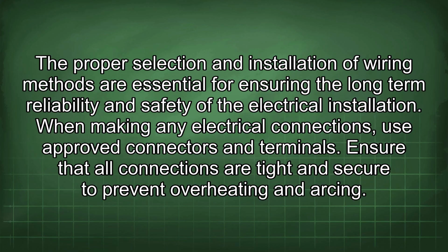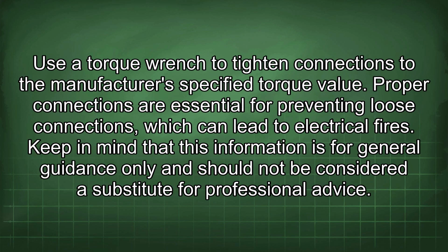When making any electrical connections, use approved connectors and terminals. Ensure that all connections are tight and secure to prevent overheating and arcing. Use a torque wrench to tighten connections to the manufacturer's specified torque value. Proper connections are essential for preventing loose connections, which can lead to electrical fires.